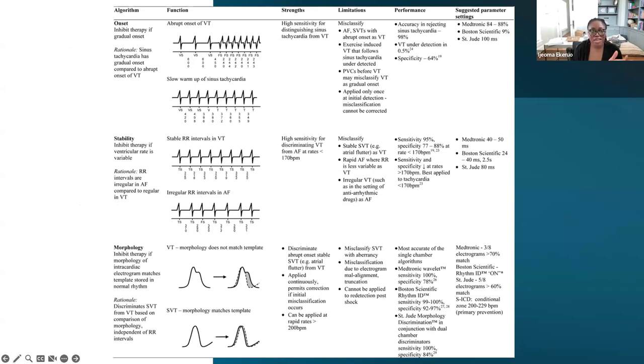Then you look at stability. In patients who have ventricular tachycardia, which most of the time is either automatic focus or circuit-based, usually there are stable RR intervals with a change of probably about 15 to 20% between cycle lengths. So typically if it's pretty stable, then it reads it as, okay, this might be ventricular tachycardia, or it still might be SVT. But what it is not is AFib or atrial flutter. With AFib or atrial flutter, the device will say, hey, I'm not going to shock that because the patient is probably stable. But if it considers that to be VT, then it'll want to shock.